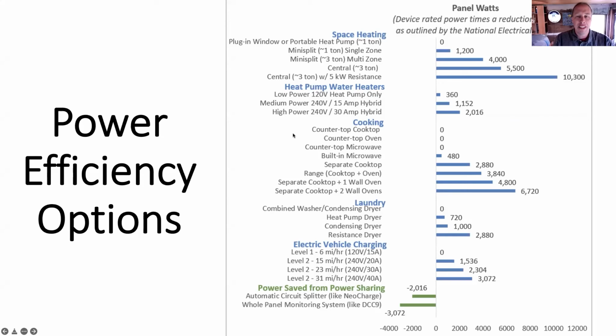This is for residences, and I'm making a calculator with my staff. We spent a year on it, working out the National Electrical Code for commercial and multifamily buildings. But I want you to see how this works in a house, where different types of systems use different amounts of power, all wattage trying to meet your space heating needs. A 1-ton portable heat pump versus a permanently wired mini split doing the same job: 0 versus 1,200 watts. A 3-ton mini split system that doesn't have to blow air uses less wattage, at 4,000, but that same 3-ton system with a central ducted system that blows air around uses 5,500 watts because of the blower.